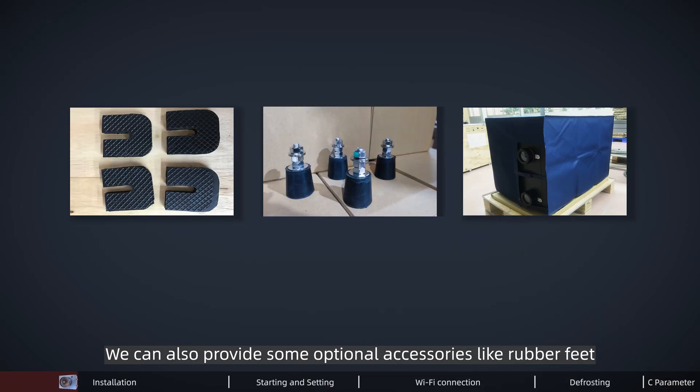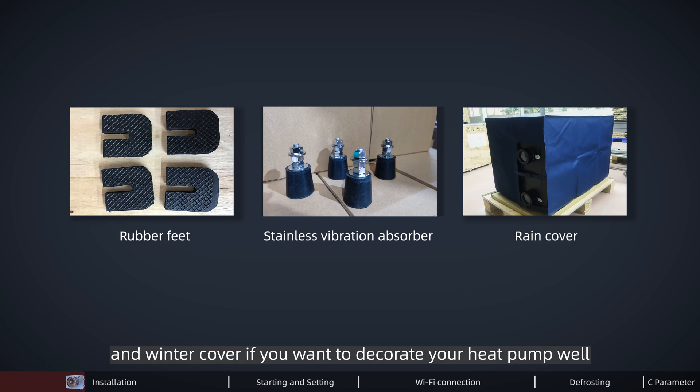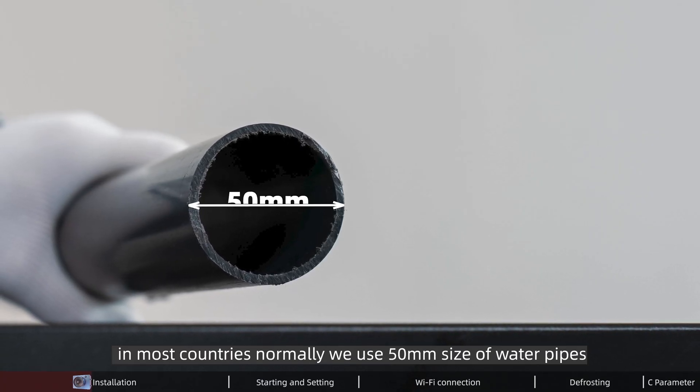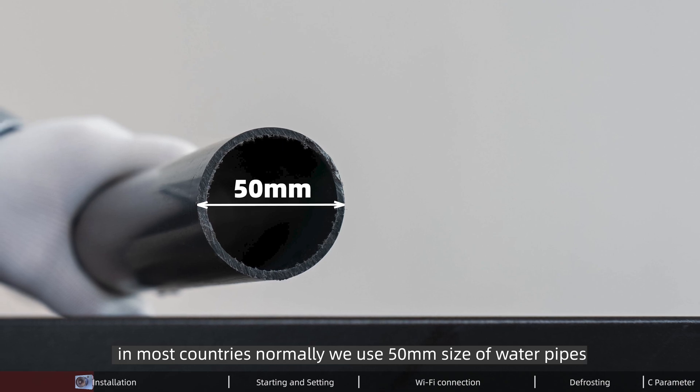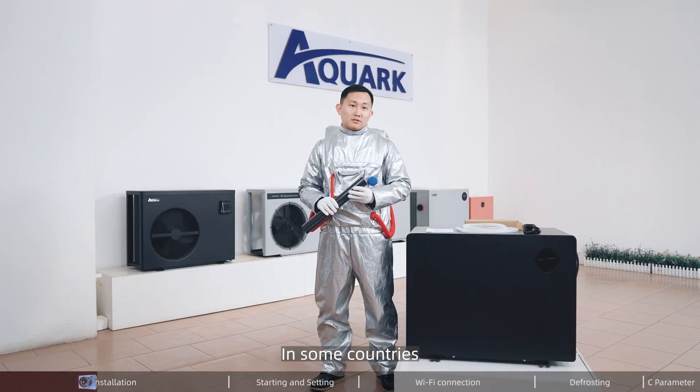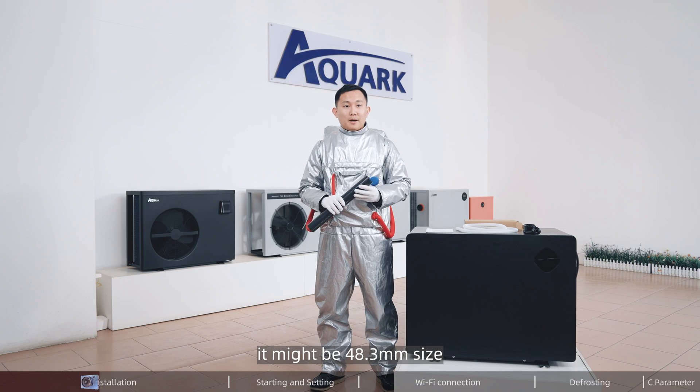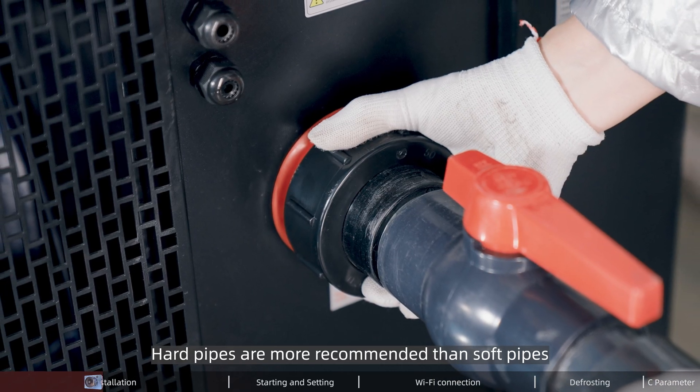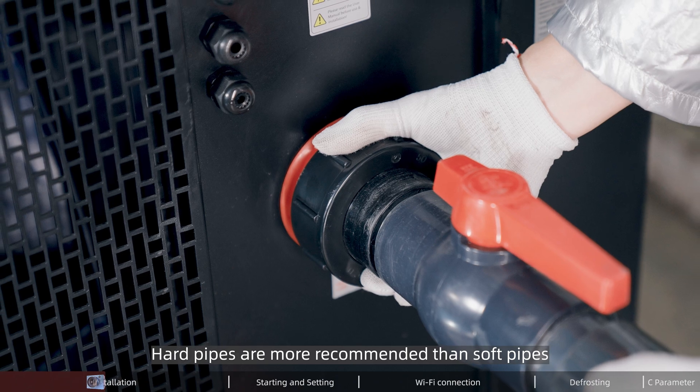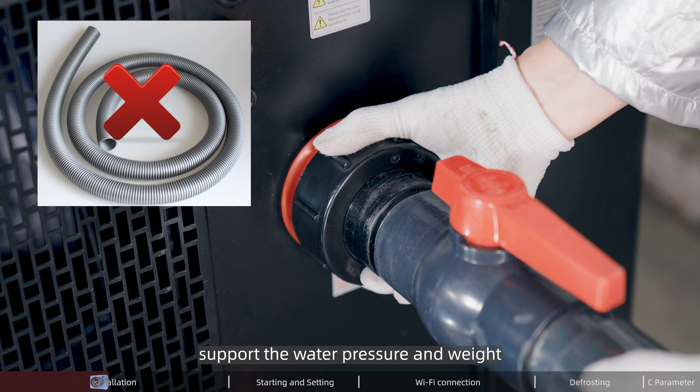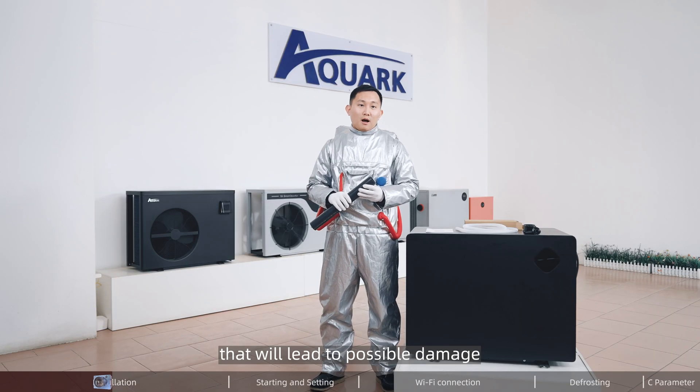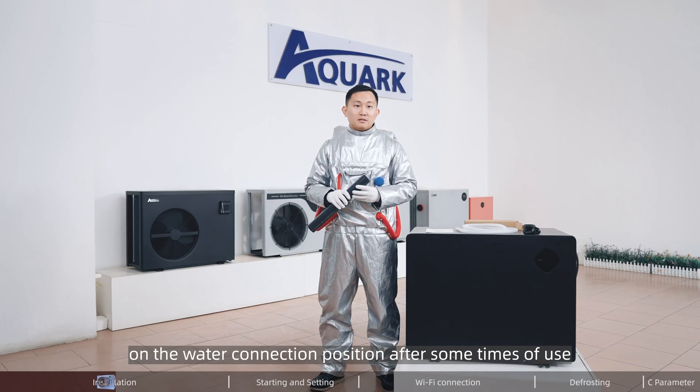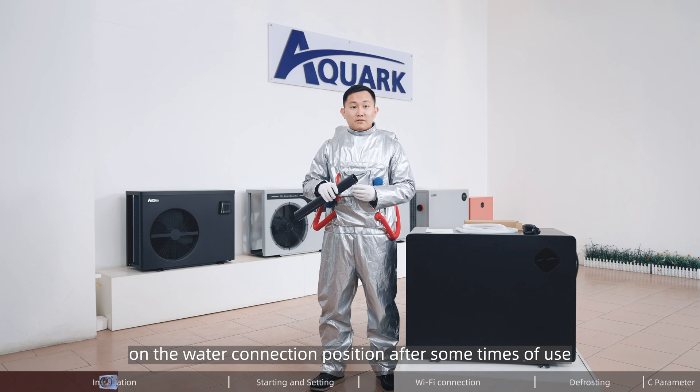We can also provide optional accessories like rubber feet, stainless vibration absorber, and winter cover. Please pay attention that in most countries we normally use 50mm size water pipes, though in some countries it might be 48.3mm. Hard pipes are more recommended than soft pipes, because soft pipes cannot support the water pressure and weight, which will lead to possible damage on the water connection position after some time of use.